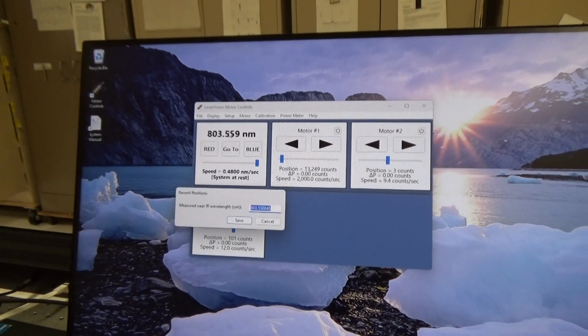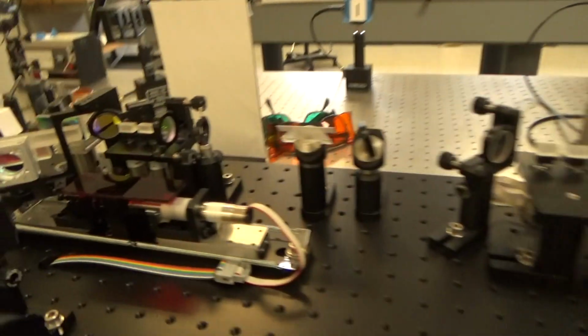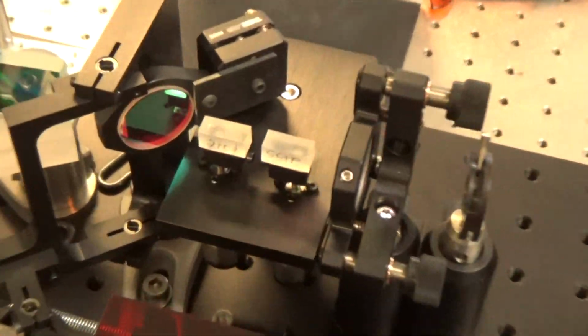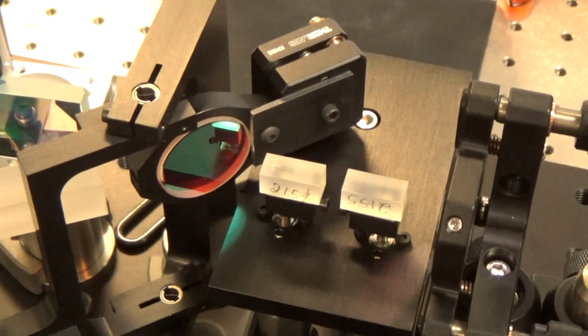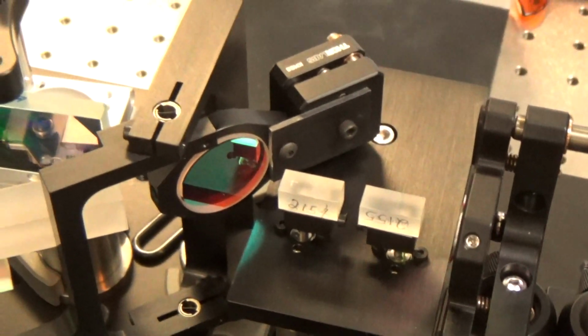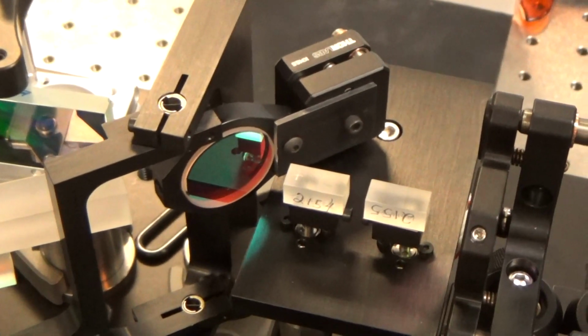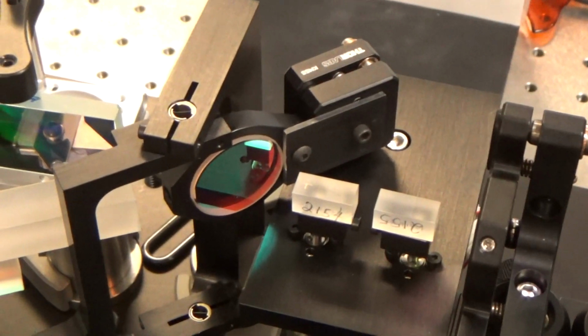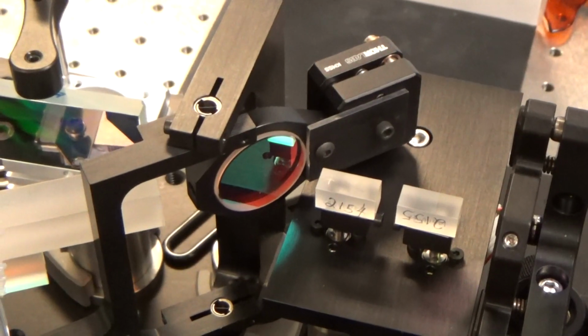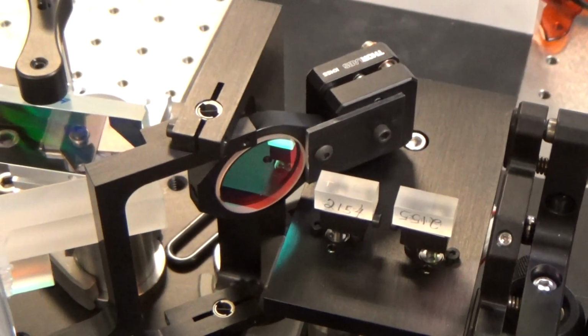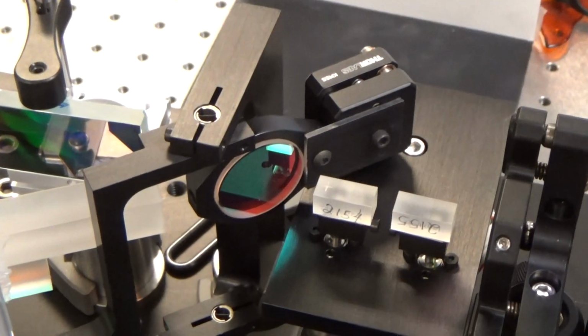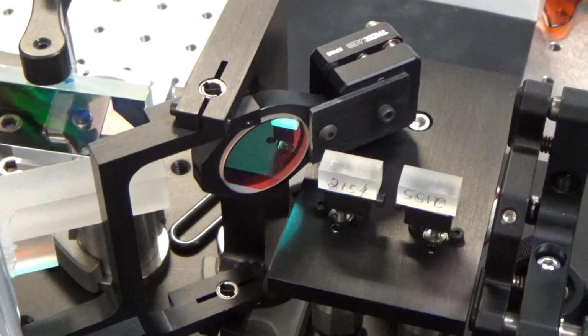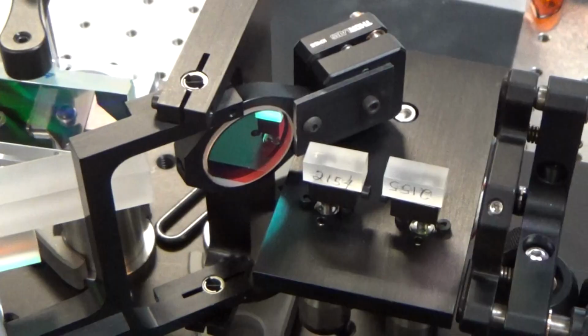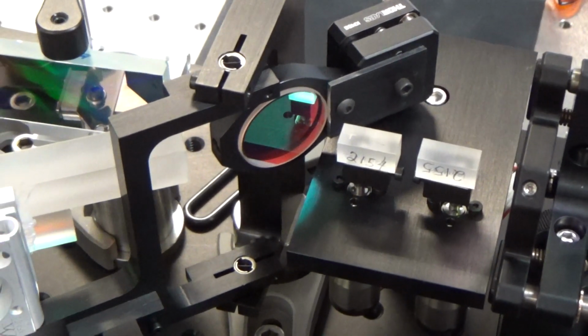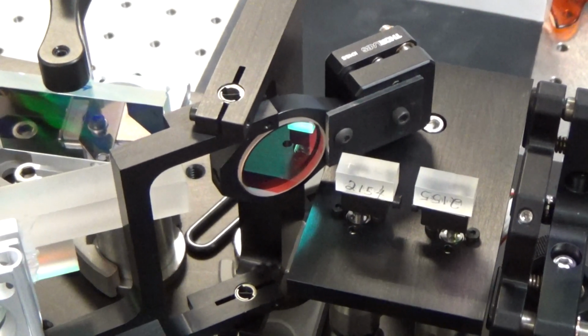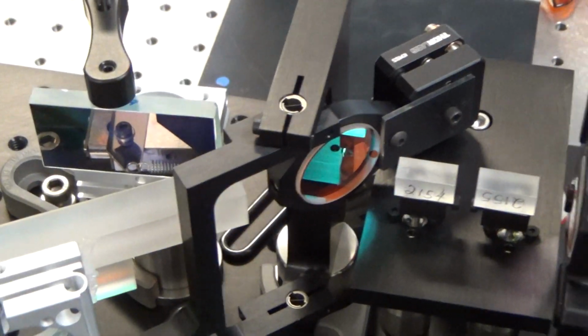What I do is slightly different. These crystals are all very reproducible, except for a slight offset in the crystal angle, depending upon how the grower has done the final cut. And so I use calibration coefficients that I've derived from using wave meters in other people's labs, and invert that so that I can use the position of the first crystal in order to determine what the operating wavelength is.